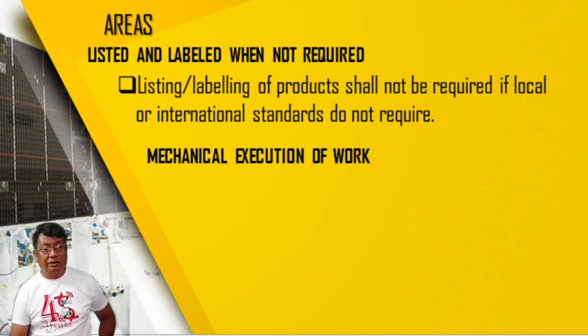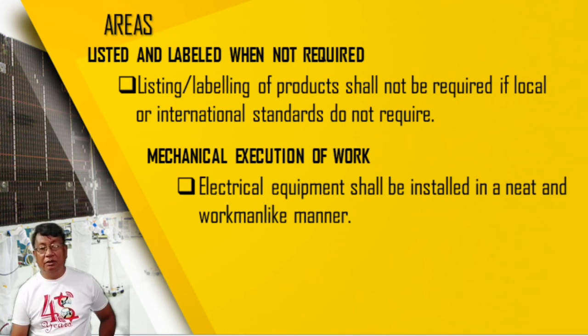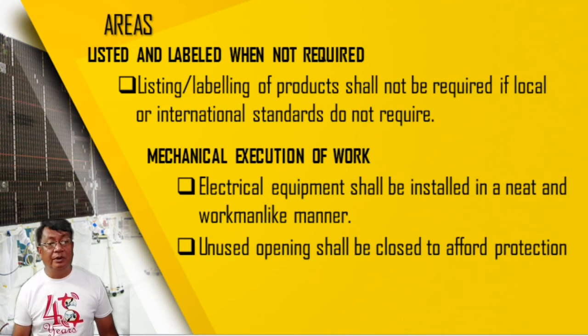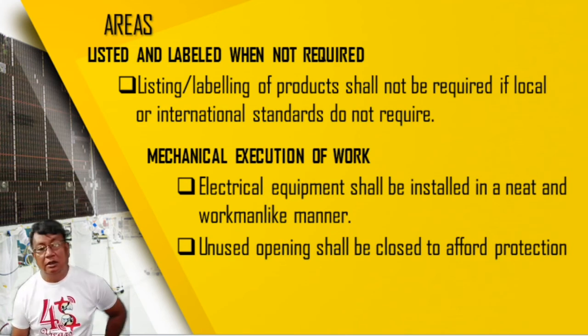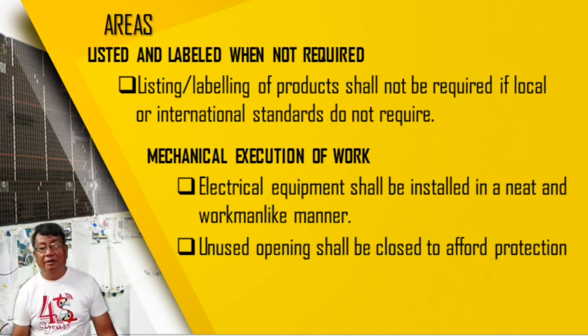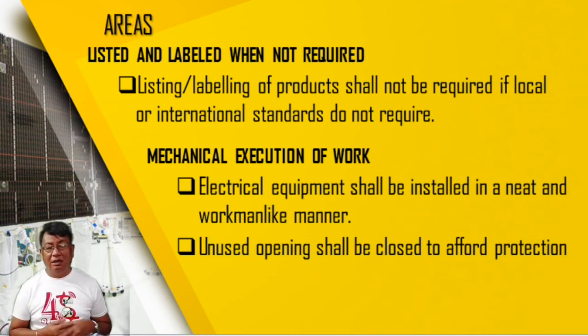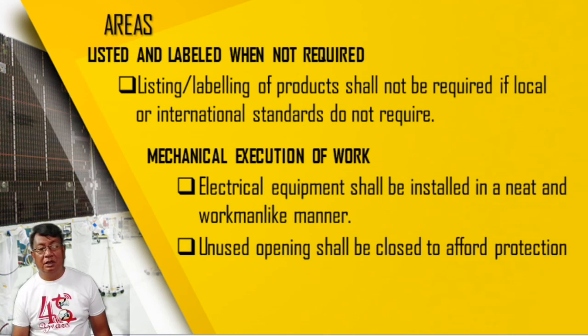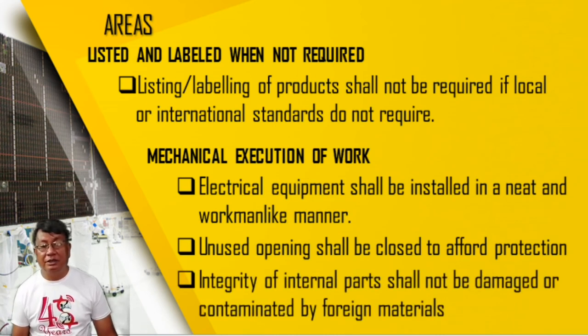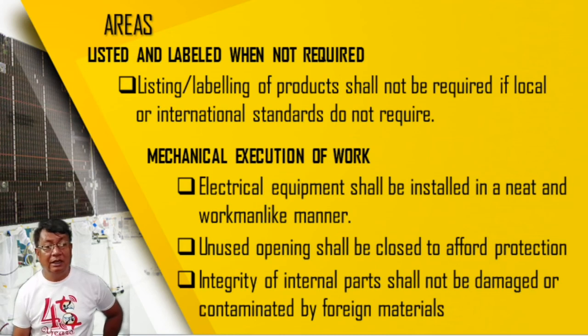So, mechanical execution of work. Electrical equipment shall be installed in a neat and workmanlike manner. So, installation should be done as neatly as necessary. Unused openings shall be closed to afford protection. If there are some openings, for example, doors, or manholes, or these boxes, the utility box, outlets, then of course we have to use closed protection. So we have integrity of internal parts: they shall not be damaged or contaminated with foreign materials.